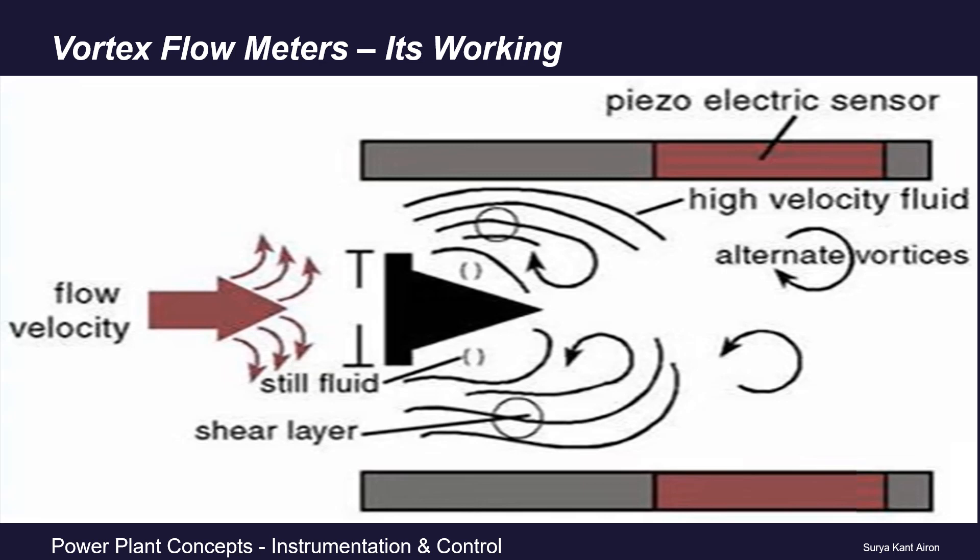The generation of vortices is known as the Kármán effect or Kármán vortices. The culmination point of these vortices will be approximately 1.2 times the pipe diameter downstream of this vortex shedder. At this particular point — 1.2 times downstream — we install our vortex detector or sensor.